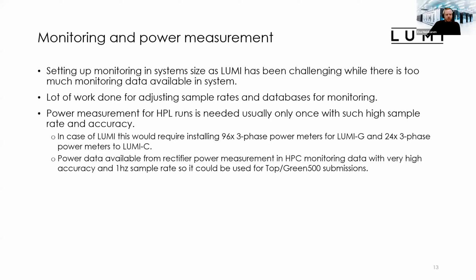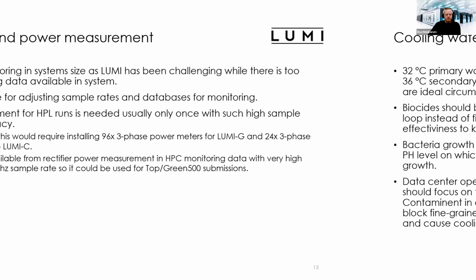A little bit about power and measurement. Setting up the monitoring system at the size of Lumi, as Samuli said, there's a billion lines of logs and many measuring points. So it has been challenging to get monitoring operational, and lots of work has been done on that part. Also, the power measurement on the HPL is only needed once with such a high sample rate and accuracy, so this should be measured from the compute cabinet itself.